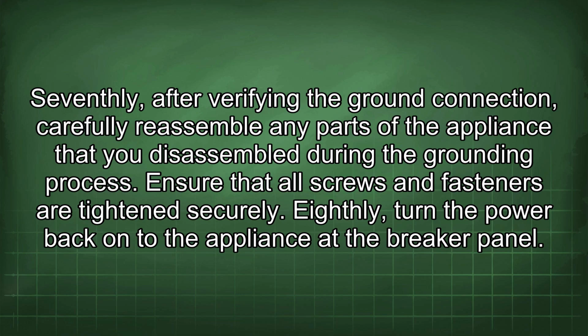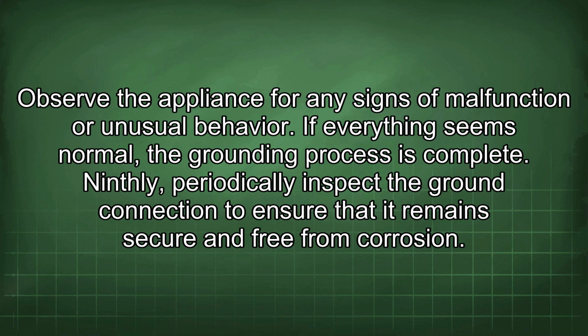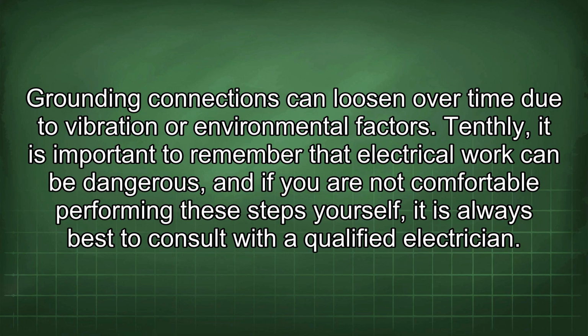Seventhly, after verifying the ground connection, carefully reassemble any parts of the appliance that you disassembled during the grounding process. Ensure that all screws and fasteners are tightened securely. Eighthly, turn the power back on to the appliance at the breaker panel. Observe the appliance for any signs of malfunction or unusual behavior. If everything seems normal, the grounding process is complete. Ninthly, periodically inspect the ground connection to ensure that it remains secure and free from corrosion. Grounding connections can loosen over time due to vibration or environmental factors.